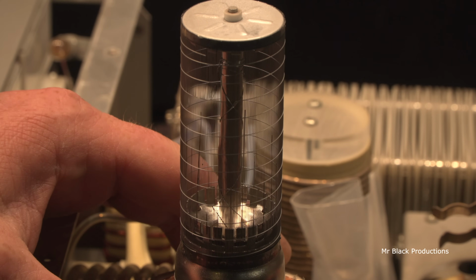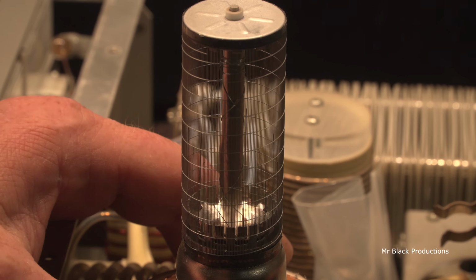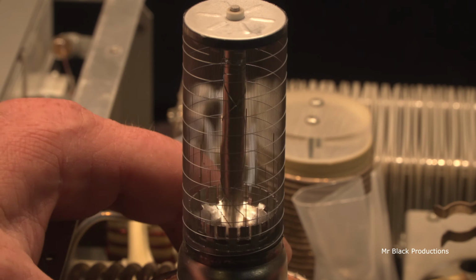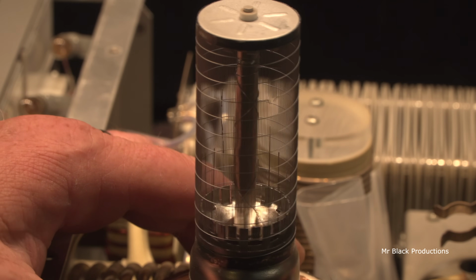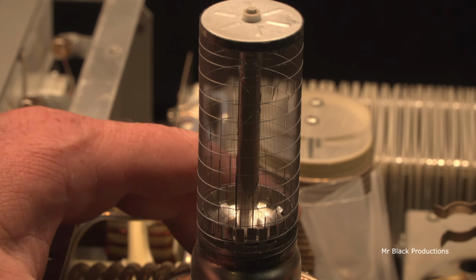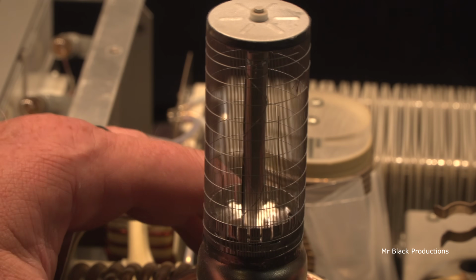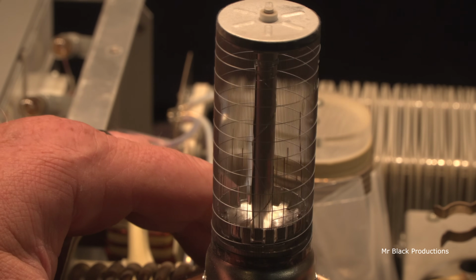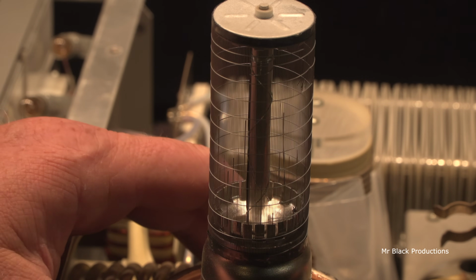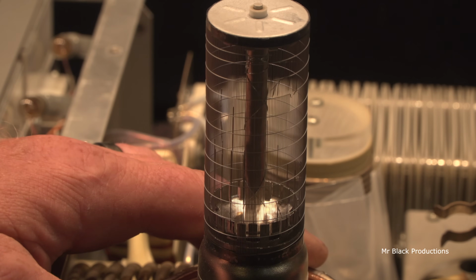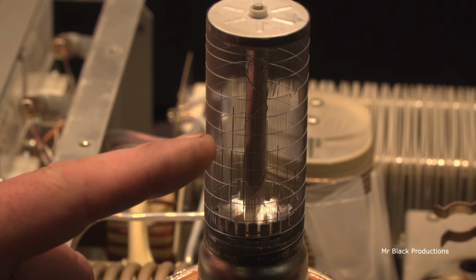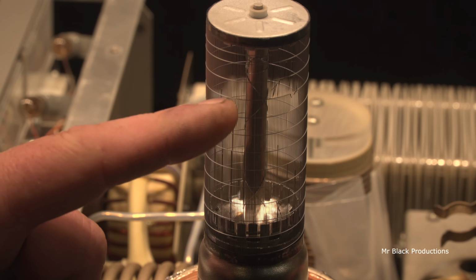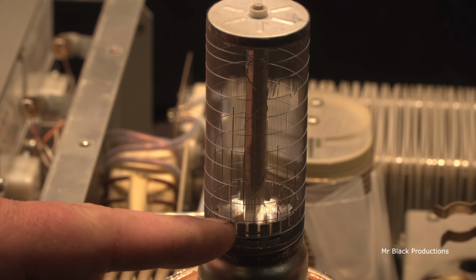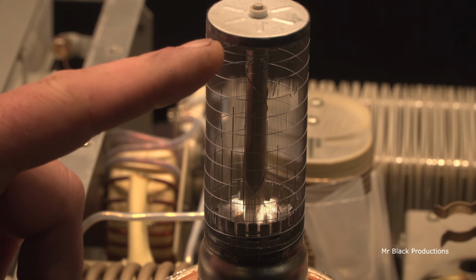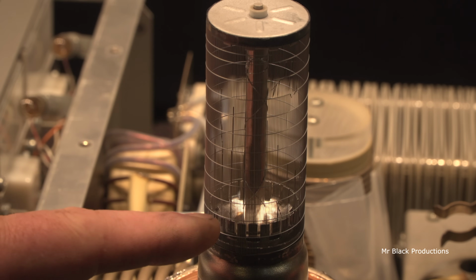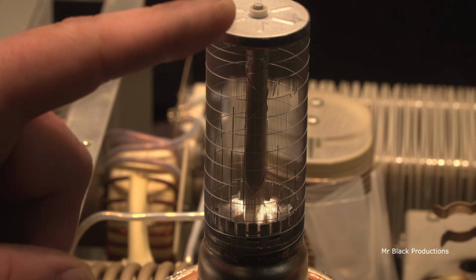You can't see it, but there's a hole right in front of you. You can clearly see there's an inner structure and an outer structure of this thing. Let me rotate this around. You see the hole? Now look at how the little tiny pieces of nichromium, tungsten, and so on are on the inside of this tube. See how the wires are broken down? You see that vertical string? For every one of these fingers here at the bottom, there's an attachment point up here on the top of the bobbin head. So that's your internal filament structure.